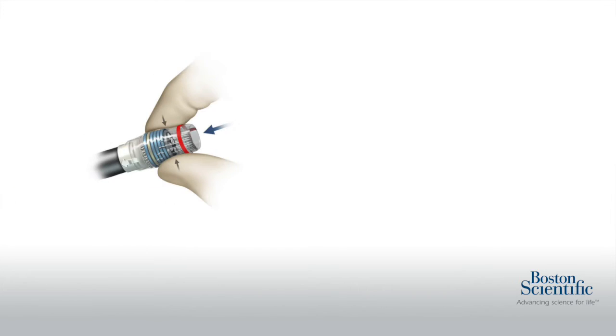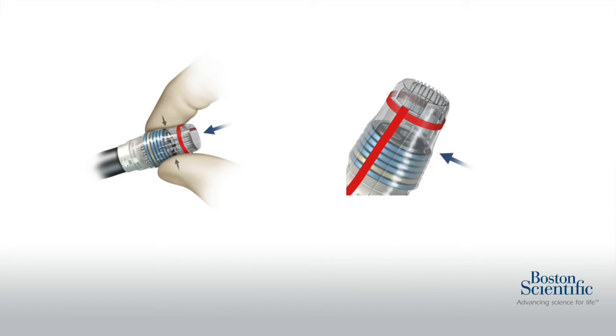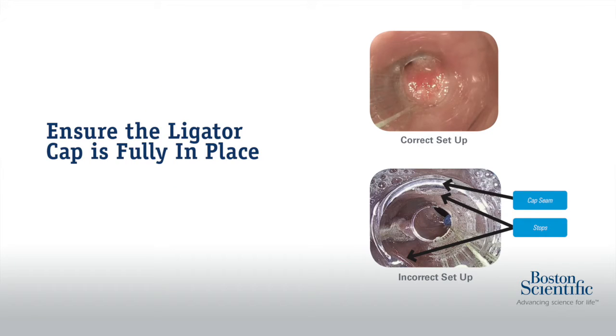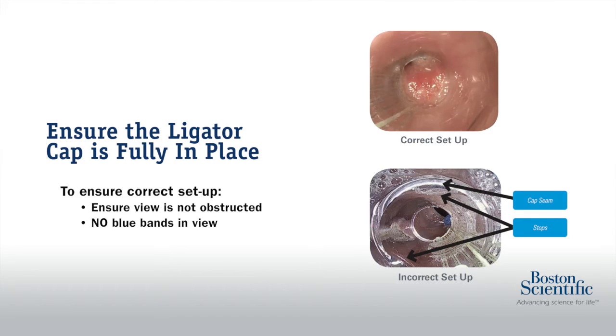The ligator cap should be pushed until the tip of the endoscope is up against the inner rim of the ligator cap, with the endoscope visible over the first band. It is important to ensure the ligator cap is fully in place. To ensure correct setup, you should have a clear, unobstructed view. Be sure that there are no blue bands in view, no stops in view, and no cap seams in view.